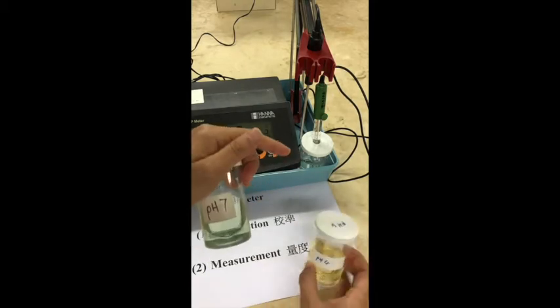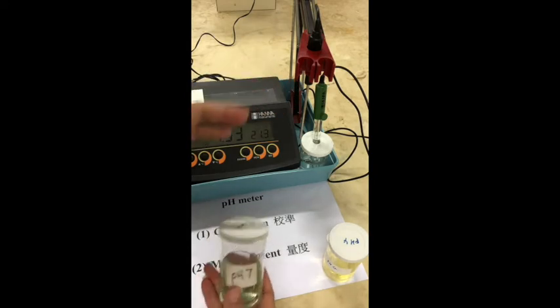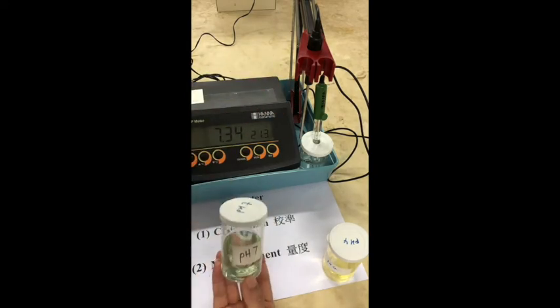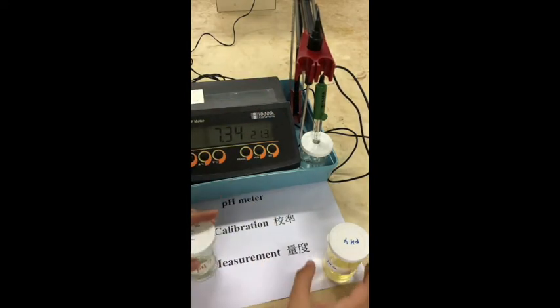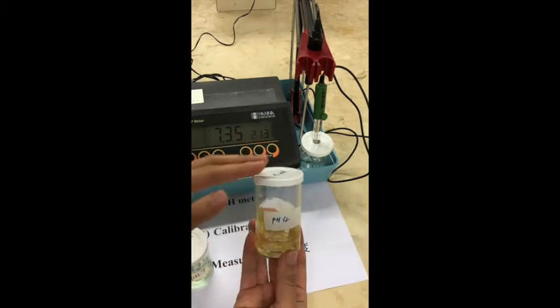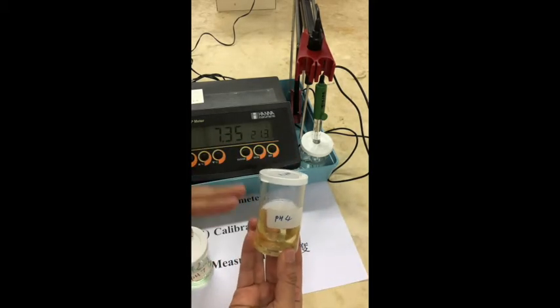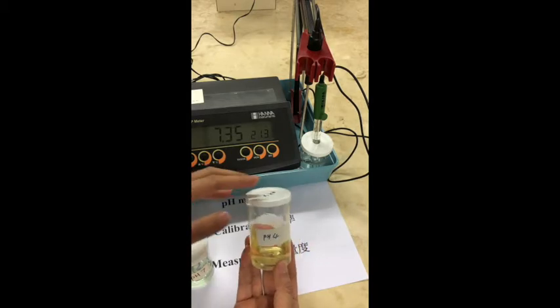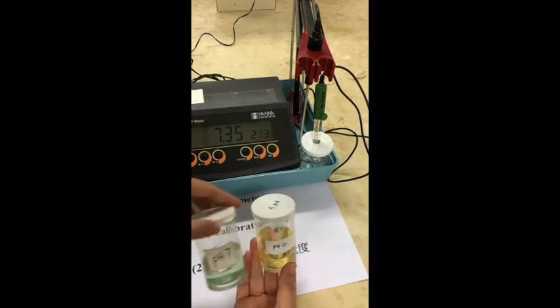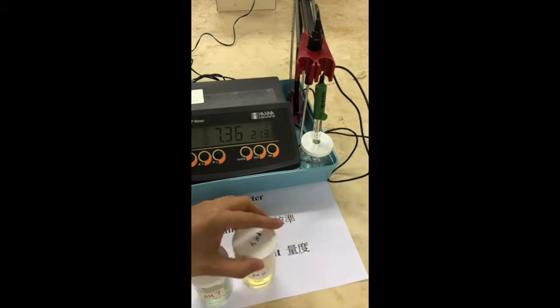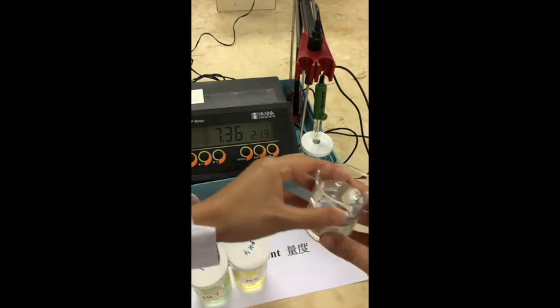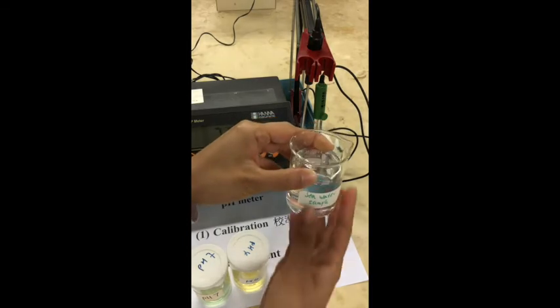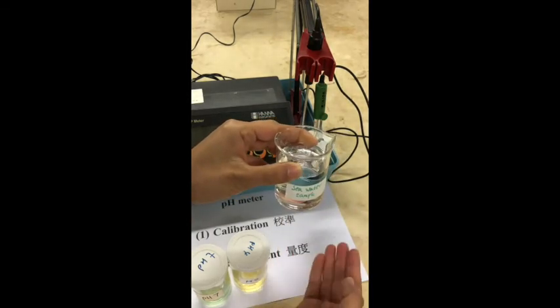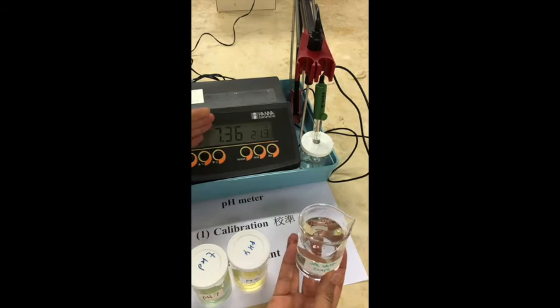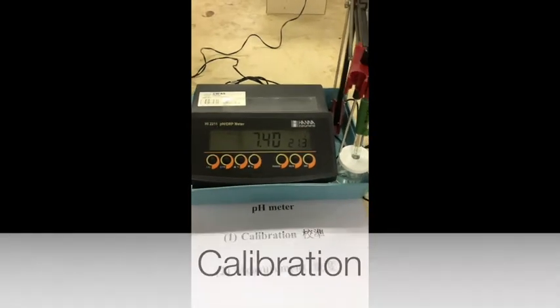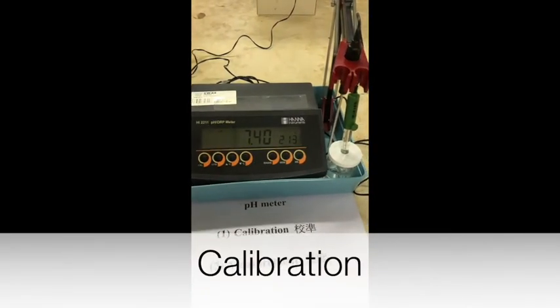During the calibration process, the electrode and the thermocouple will be placed inside the pH 7 buffer. The potential will be recorded by the instrument. After that, place the electrode into the pH 4 buffer. Another potential will be recorded. Two data points will be used to construct the internal calibration curve. For the sample measurement, the pH will be obtained by substituting the electrode potential of the solution into the calibration curve automatically. Okay, let's start the calibration procedure.